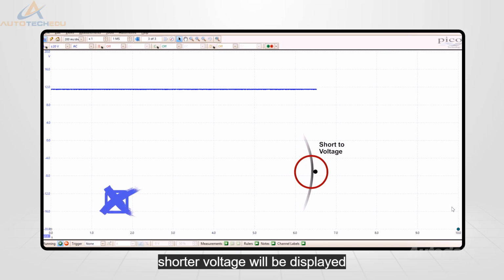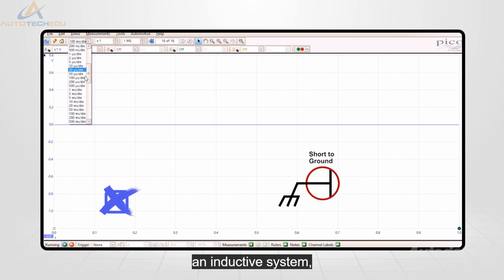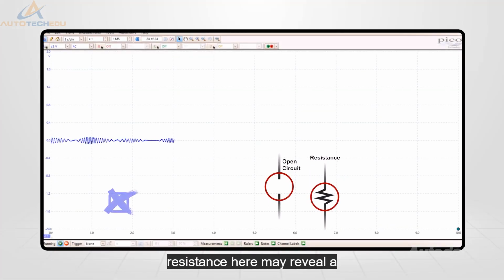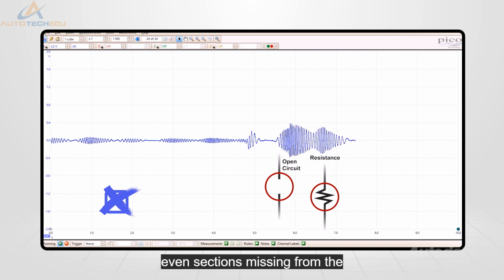A short to voltage will be displayed as a constant voltage on the screen. If there was a short to ground in an inductive system, the trace will remain at zero. An open or excess resistance here may reveal a reduction in the amplitude or even sections missing from the waveform.